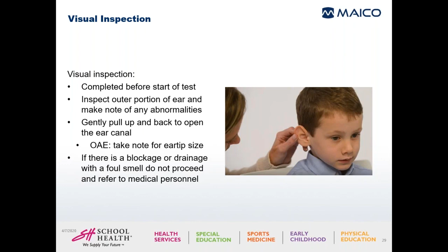As far as inserting the probe with the infants, which is about 6 months and younger, you have to pull back and down on the ear. And with the older kids, 6 months and older, you're going to be pulling up and back on the ear. That's just to straighten out that ear canal as you're placing that probe in place. When you're putting it in place, you're going to be inserting it towards the nose, kind of twisting it in. Once you have it in quite a ways, then you're going to push it back. That's because we have a little curve in our ear canal, and that directs the probe in the direction that it needs to go.